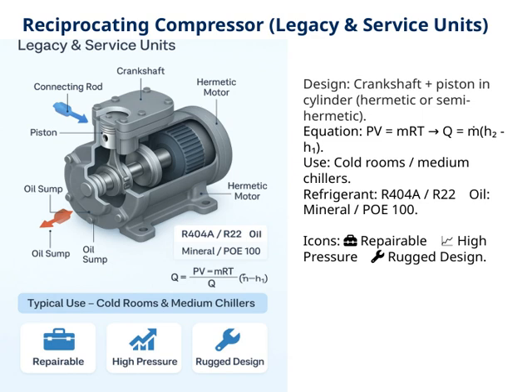Now, looking at the icons on the slide, you'll notice that these units are repairable, which means maintenance or part replacement can be managed effectively. They operate under high pressure, so safety and robustness are key, as indicated by the rugged design icon. This combination of features makes reciprocating compressors a versatile and dependable choice for medium-scale cooling needs.